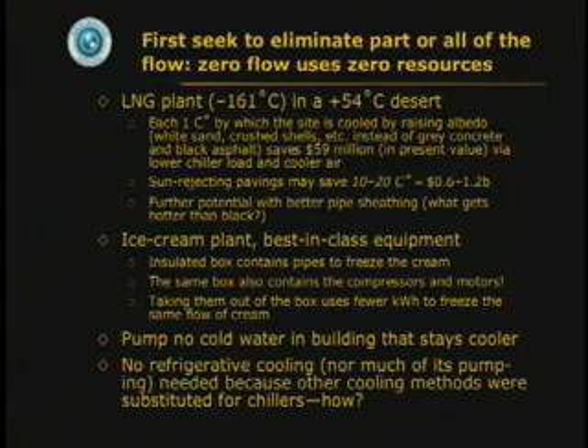You don't need to pump chilled water to chill a building that stays cooler because it has better windows, better insulation, better lights and office equipment. And in fact, if you substitute other methods of cooling, you won't need the chillers in the first place. For example, maybe you can get free cooling out of the air or by evaporating water in a cooling tower or otherwise. And that way, with a really well-designed system for $100 per refrigerative ton of capacity, you can get 125 or so units of cooling per unit of electricity. That is well over 10 times what the best chiller system will do under very favorable conditions.